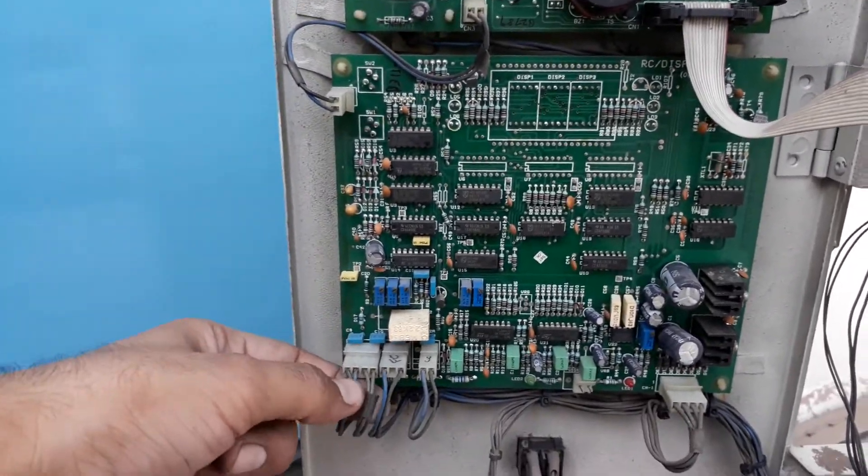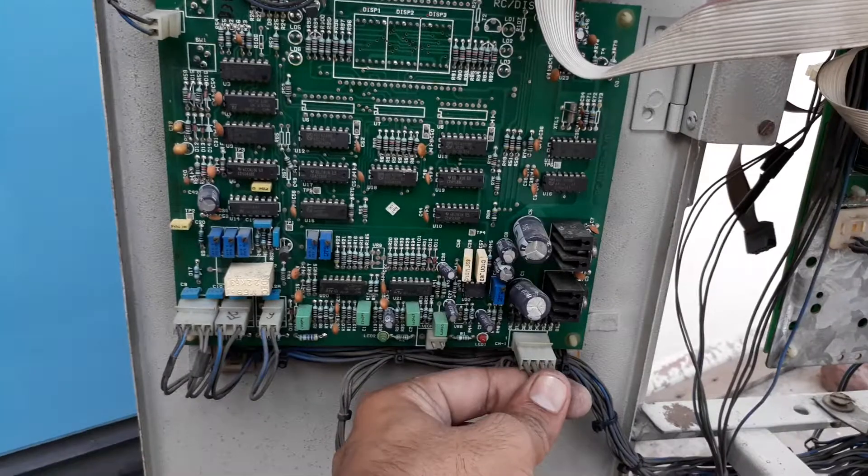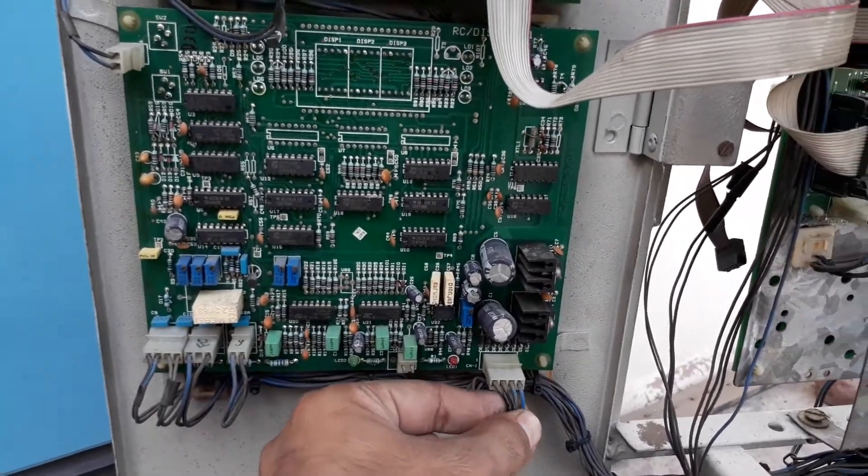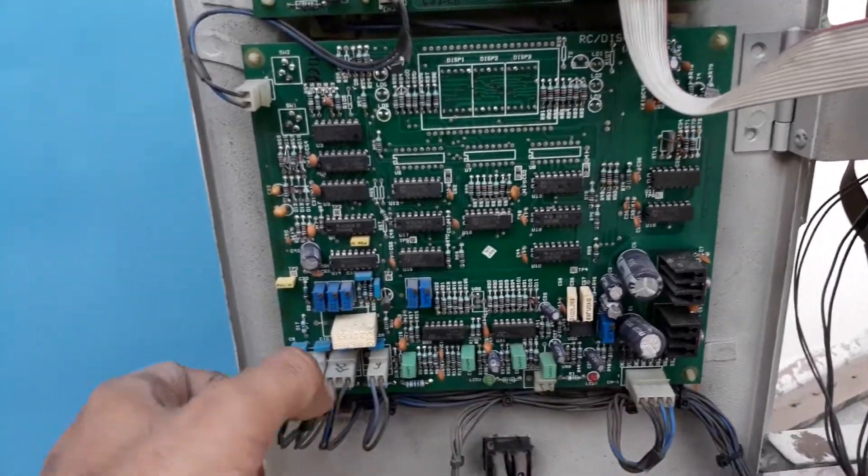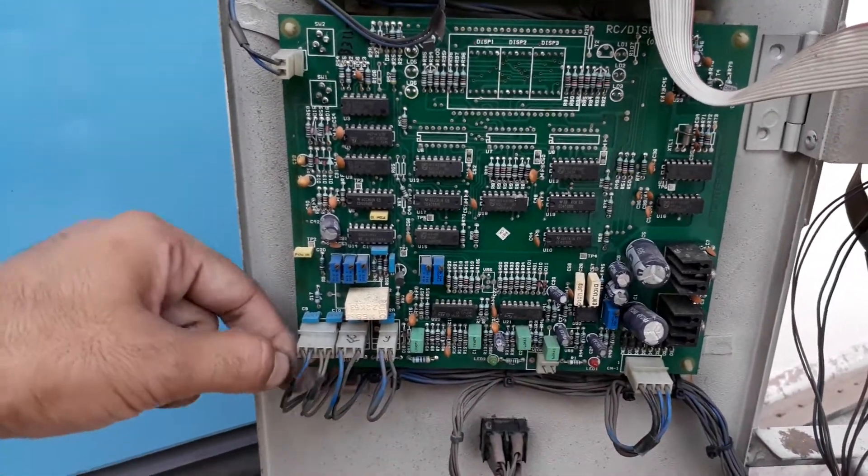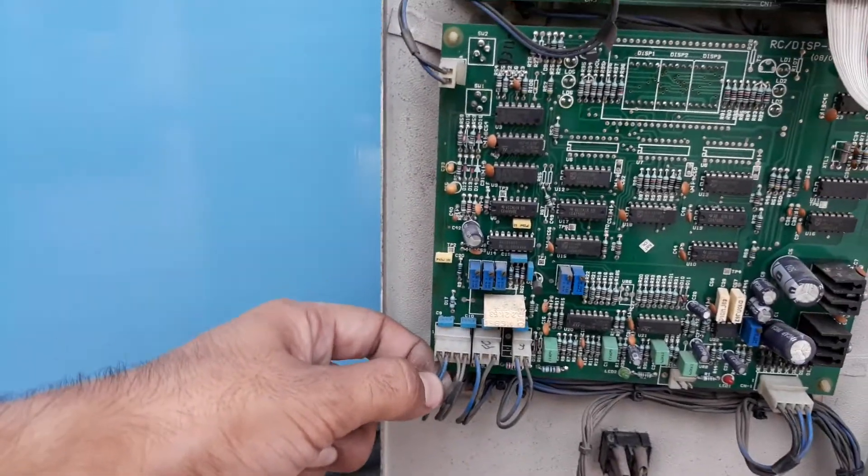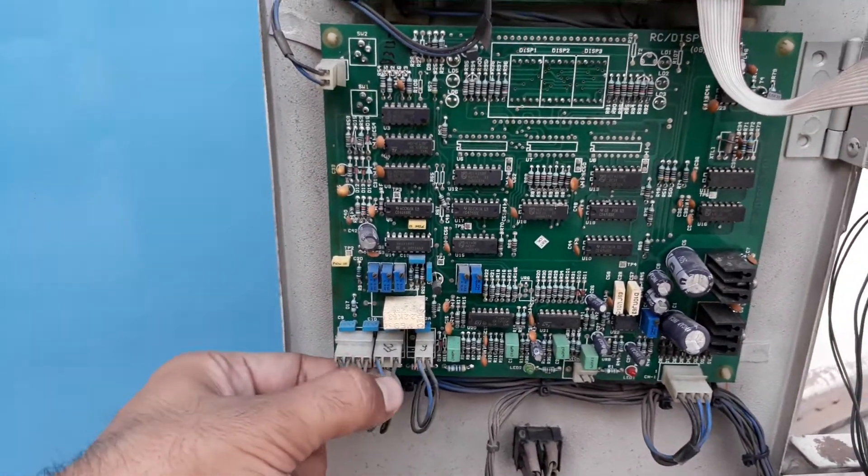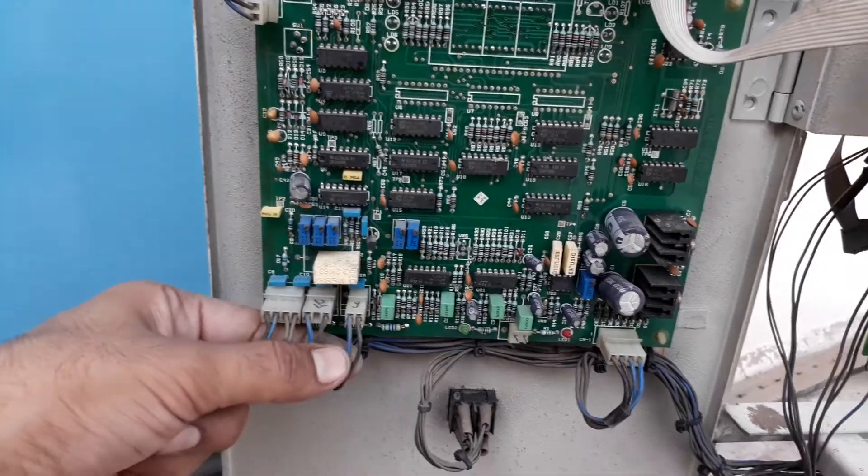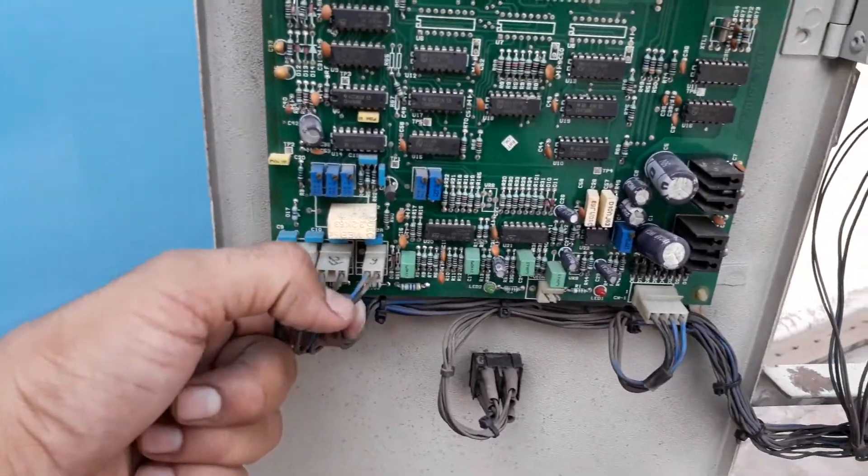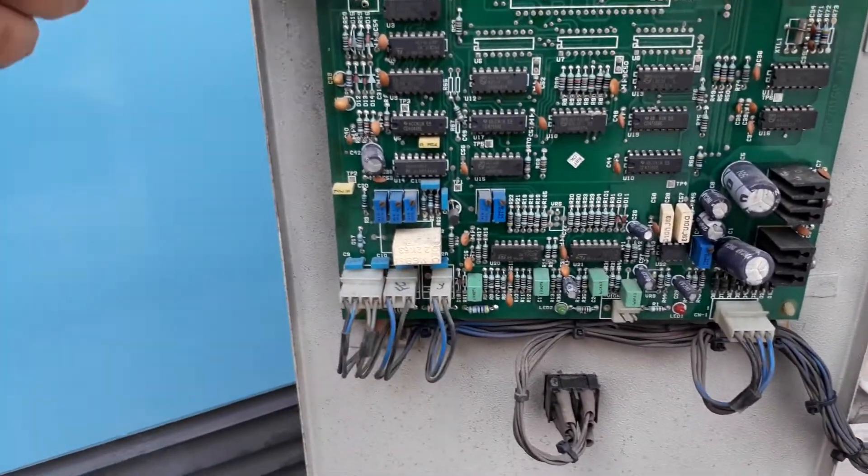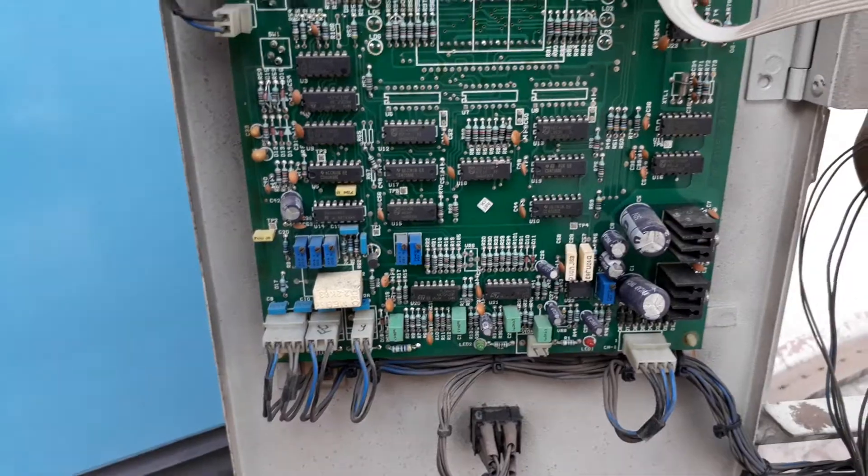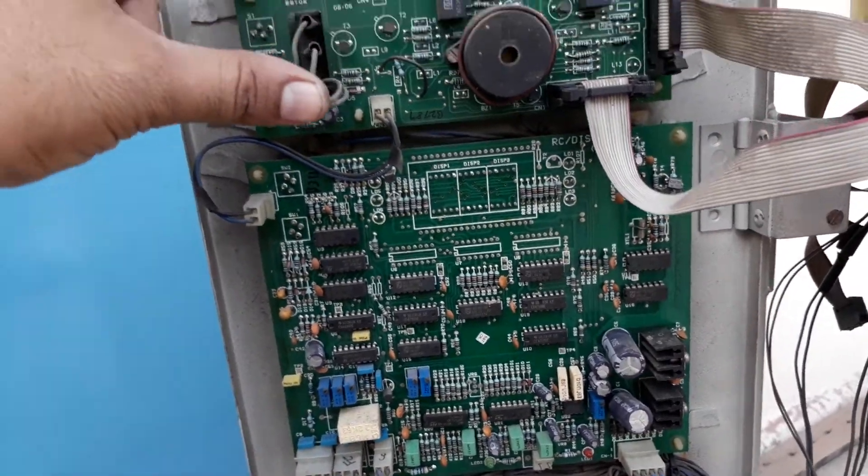Very simple. This is the input supply through a transformer step-down voltage. Here they fitted the input and output voltage monitoring. This is for output current and this is for DC voltage. The DC voltage signal goes to this card.